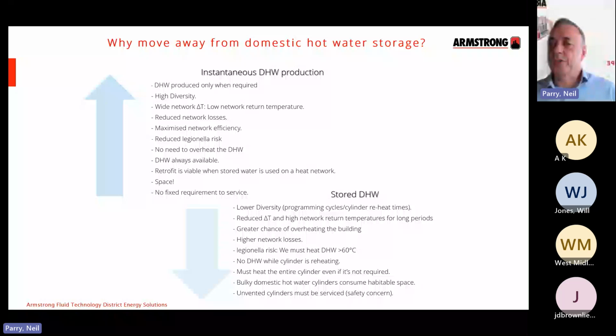And of course, we now have parity in the UK where the HSE, NHBC, CIBSE CP1 are all suggesting 50 degrees C from an instantaneous HIU because it's classed as a low Legionella risk, because point of use hot water generation only occurs when you actually want it.